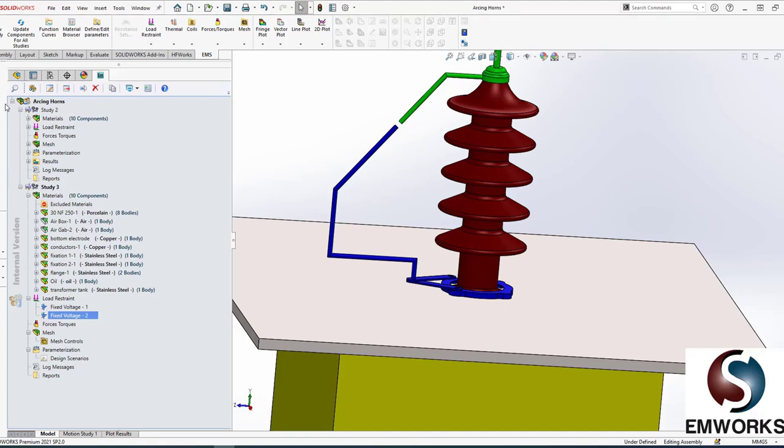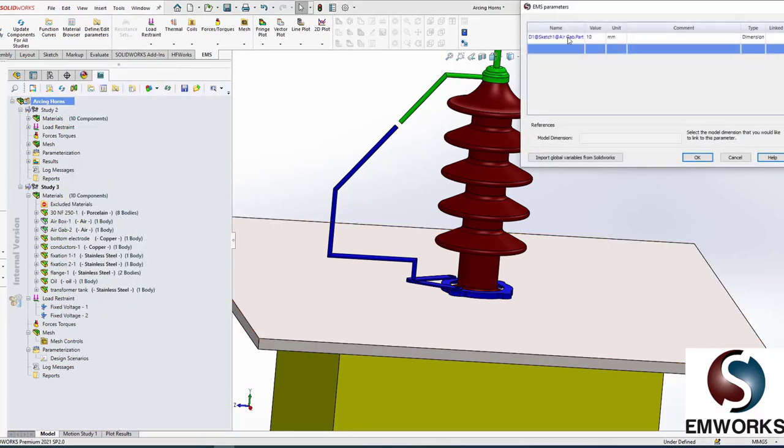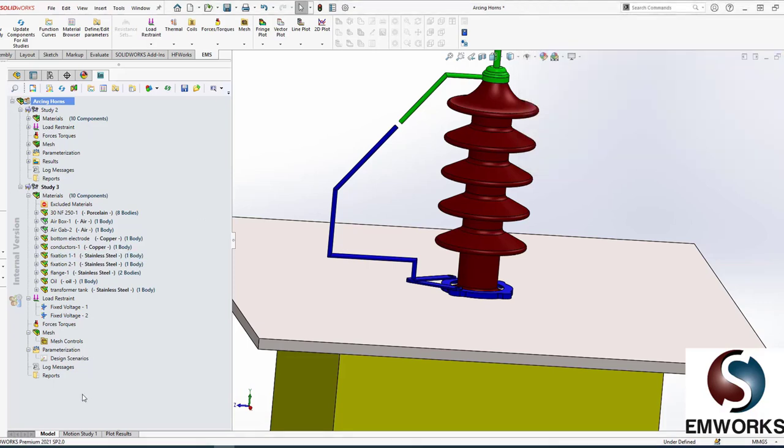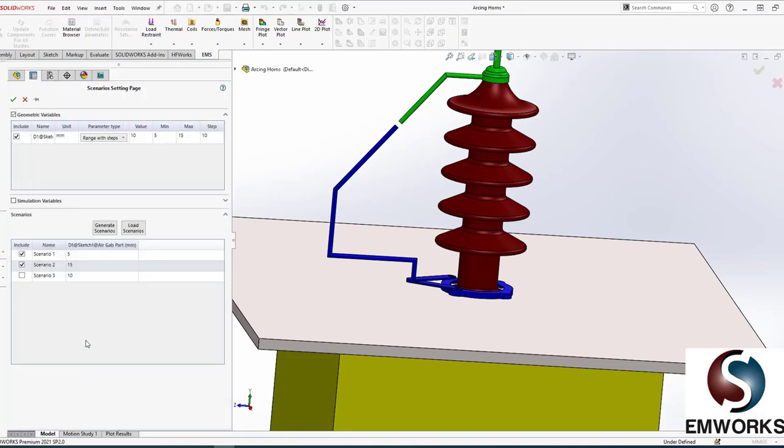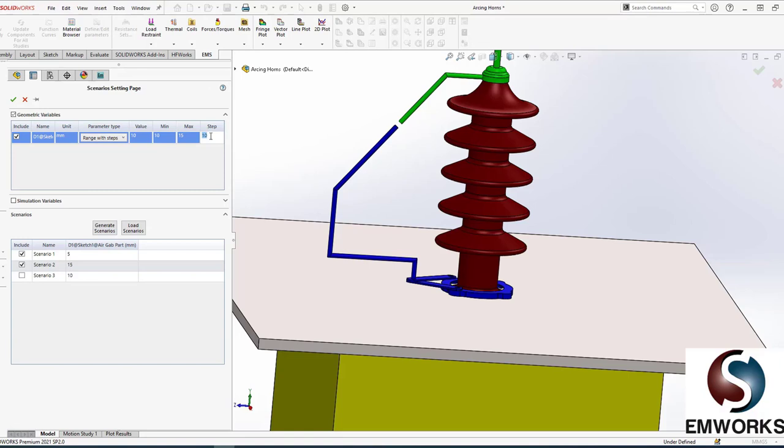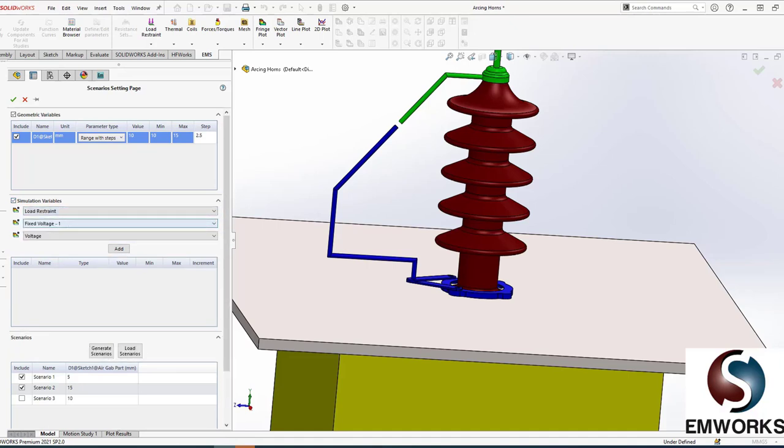If you want, you can put symbols, change the color. The next load or restraint is the high voltage. This is my high voltage, and actually I want to apply 10,000 volts. This particular insulator operates up to 10,000 volts. So again, if I want some symbols, I can put my symbols just to see where boundary conditions apply. That's all I need because the meshing is automatic, the material is copied, and I have only two boundary conditions. Now there is one step that you have to do: the parameterization. Right-click on the root of the tree and say parameters.